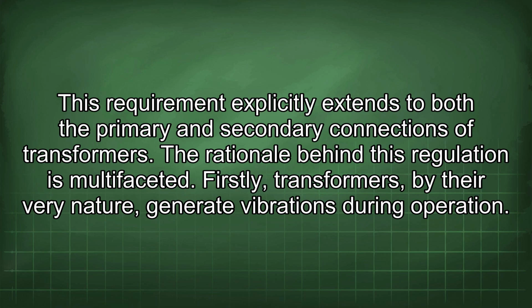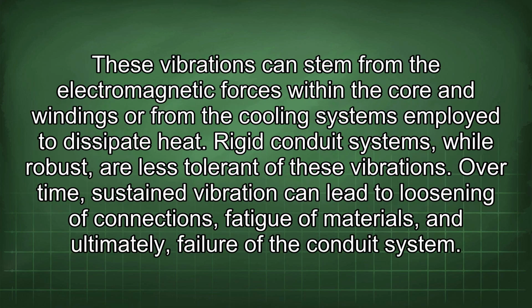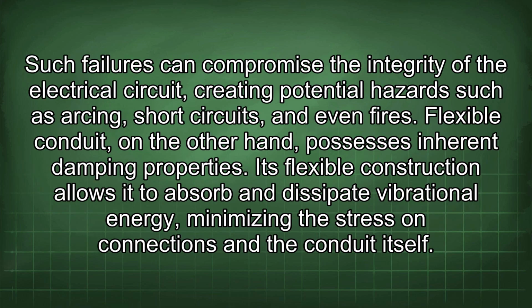Firstly, transformers, by their very nature, generate vibrations during operation. These vibrations can stem from the electromagnetic forces within the core and windings or from the cooling systems employed to dissipate heat. Rigid conduit systems, while robust, are less tolerant of these vibrations. Over time, sustained vibration can lead to loosening of connections, fatigue of materials, and ultimately, failure of the conduit system. Such failures can compromise the integrity of the electrical circuit, creating potential hazards such as arcing, short circuits, and even fires.